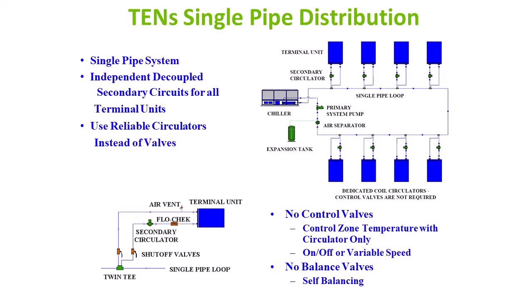That's important that it's a single pipe, because what we're trying to do here is allow the building owner or homeowner an opportunity to take heat off of or put heat back into that line, just like you would natural gas. If we had a two-pipe system that required balancing, every time we added a building onto it we'd have to go in there and rebalance the system. That's not too good. So a single pipe's biggest advantage is it's self-balancing. I can add any number of units wherever I want, at the beginning or end of the loop, and everybody's just happy.